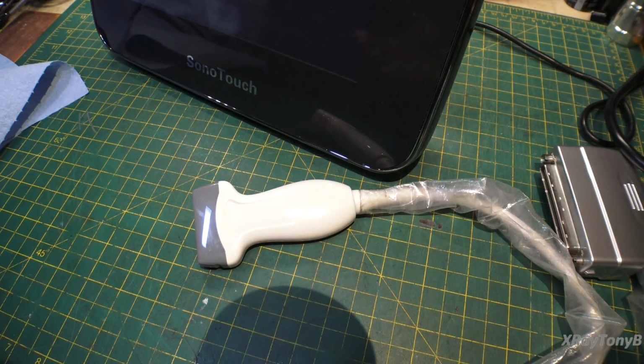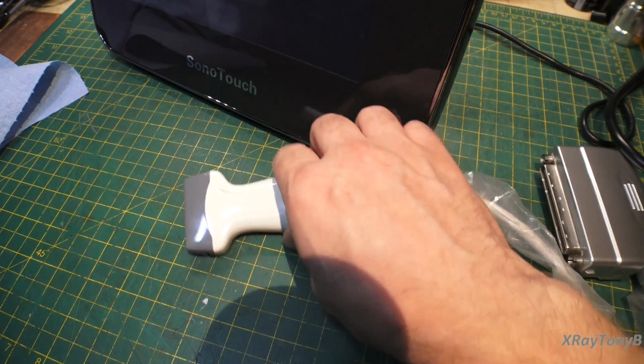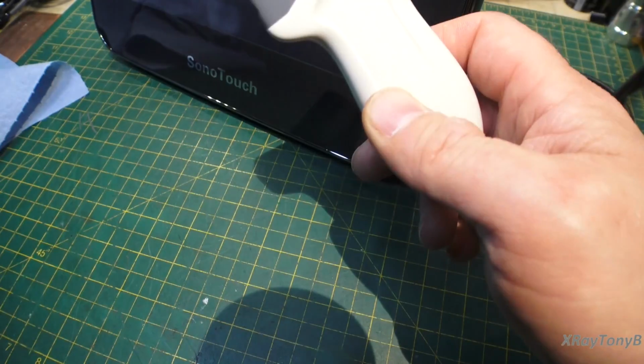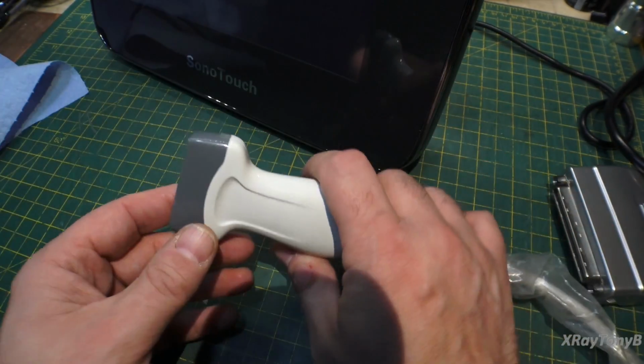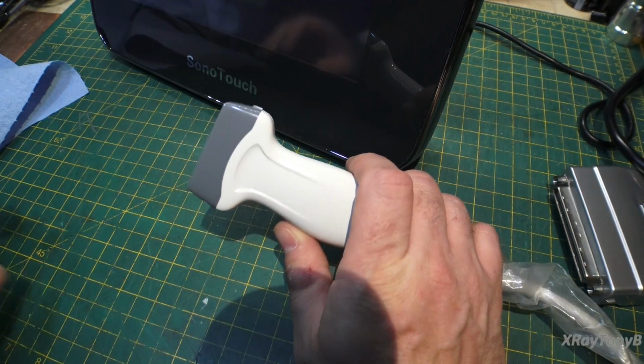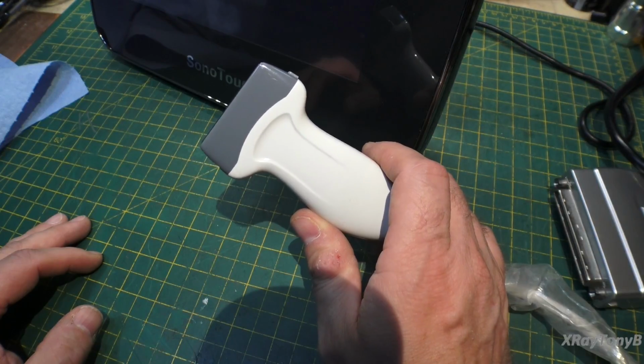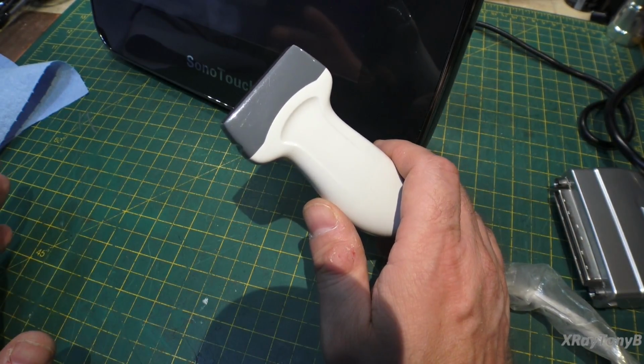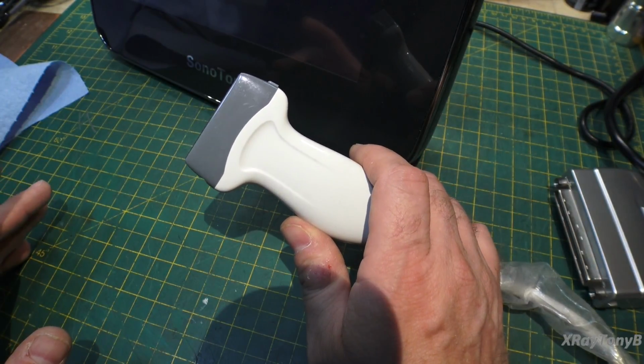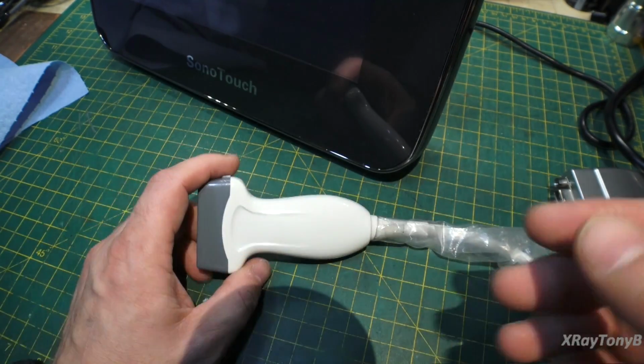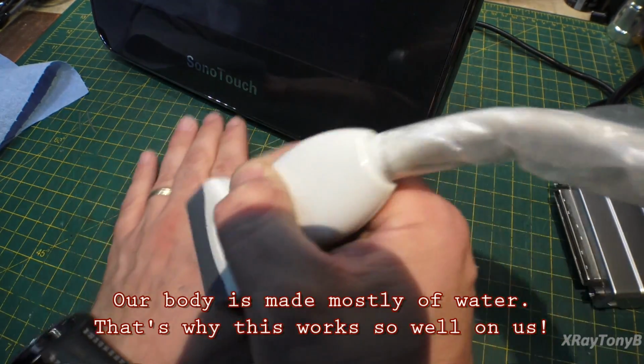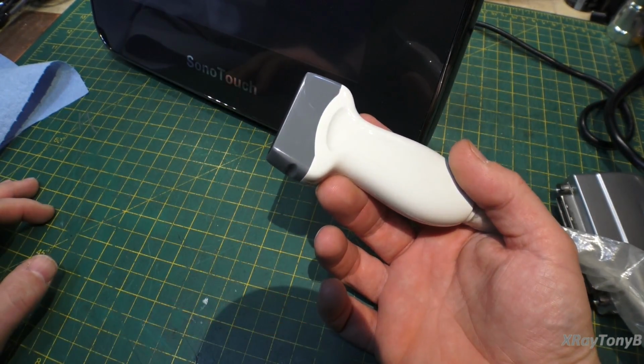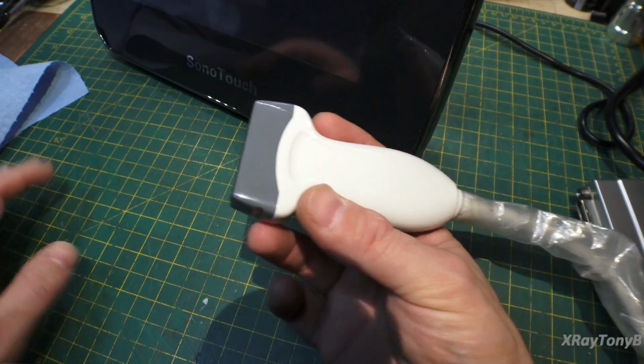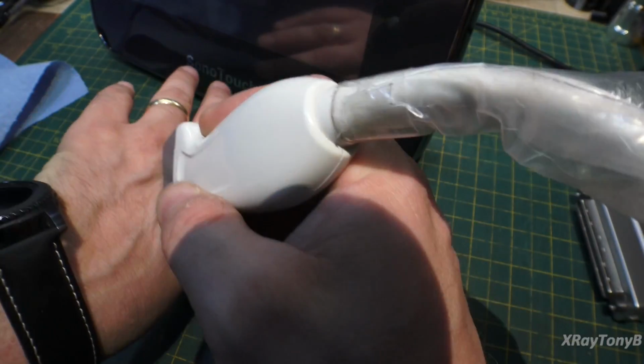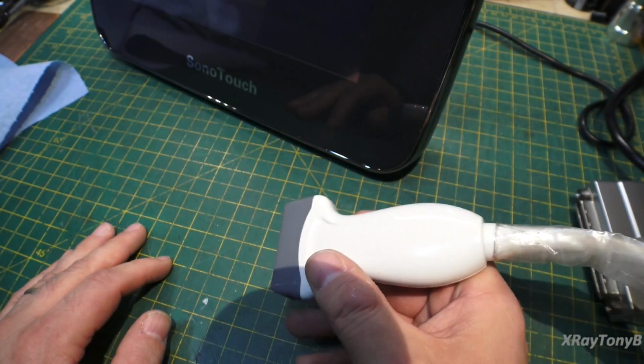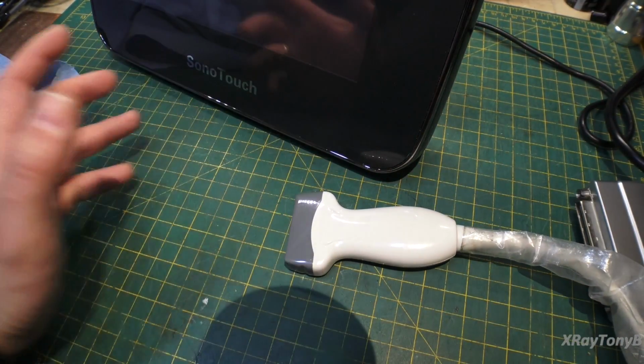Okay, even though space is a vacuum, electromagnetic waves will travel through it. If we took this into outer space and turned it on, nothing would happen. Nothing would come out of it because you need a medium for it to propagate through. And it's so much so that even air is a very poor conductor of ultrasonic frequency. So you even need something closer to water. Water is a very good propagator of ultrasound. So that's why, if you ever notice, they actually put that gel on you before they put the probe on. And the reason that they do that is because that gel actually sonically couples the window of this crystal to the body part that you're trying to image. Okay, I hope that makes sense. So if we don't use that, it's not going to work.